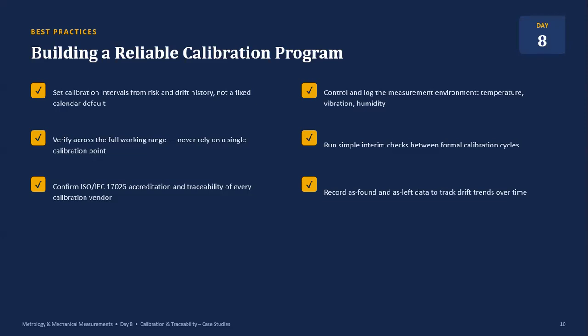A strong calibration program should be based on risk, actual drift history, and instrument usage rather than routine assumptions. Measurements should be verified across the full working range. Calibration vendors should have appropriate ISO accreditation and traceable reference standards. Environmental conditions should be controlled and recorded. Interim verification should be performed between formal calibration cycles, and both as-found and as-left data should be documented for future analysis.